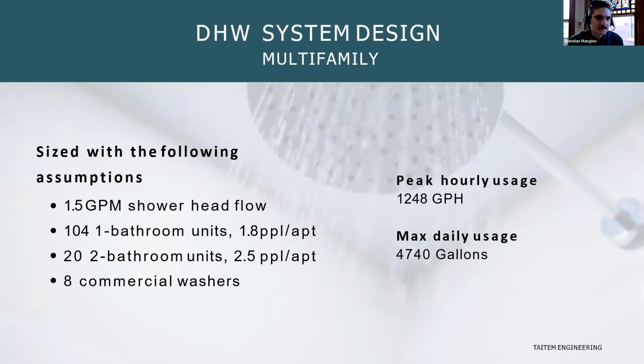So when sizing this system, I sized it under the following assumptions: 1.5 GPM shower heads, 104 one-bathroom units with an average of 1.8 people per apartment, and then 20 2-bathroom units with 2.5 people per apartment. There's also 8 commercial washers, 2 on each of the residential floors. And this output a peak hourly usage of 1,248 GPH and a max daily usage of 4,740 gallons. We used a couple different sizing calculators to come to this number, but they're all about the same. They're all based off of the ASHRAE sizing and HVAC applications.